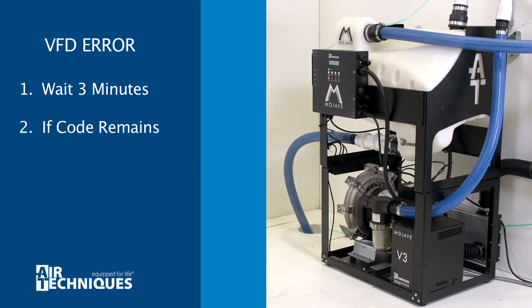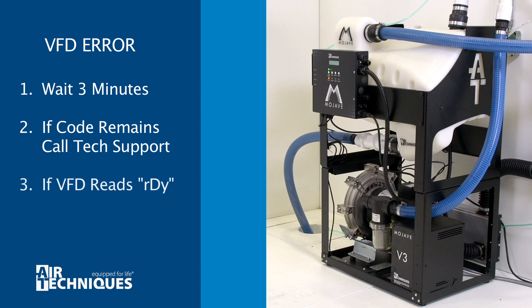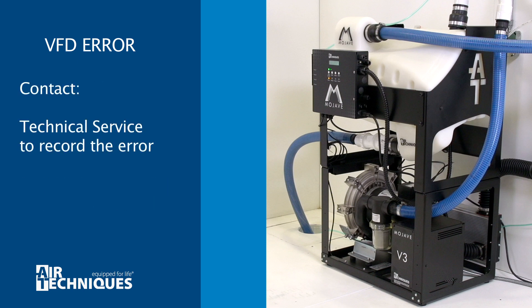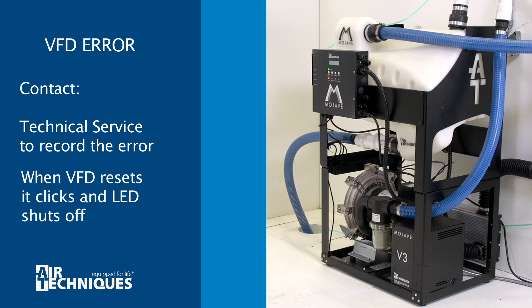If the code remains, contact Technical Service. If the VFD shows RDY, the error has been cleared and the pump will turn back on. Contact Technical Service and let them document the error code and provide suggestions. When the VFD totally resets, it clicks and the LED on its front panel shuts off.